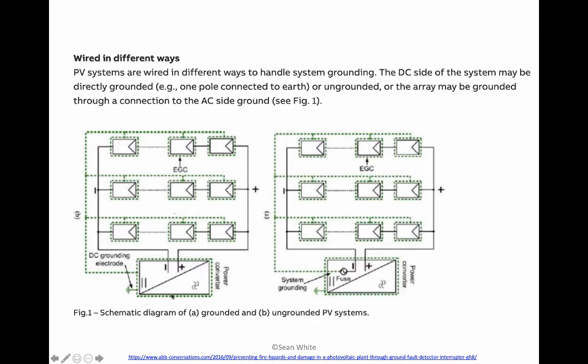We used to call these kinds of inverters European inverters because they were using them a lot in Europe, but Americans, we were afraid of them. They were called ungrounded in the National Electrical Code, and ungrounded sounds kind of scary to somebody that's a traditional old-time electrician. However, since the formerly known as grounded inverters, now known as fuse grounded, functionally grounded inverters, there were some fires, and some of those fires didn't kill anybody that anybody's heard about, but it's just not good to be starting fires. And if it was a fire in a ground mount, it's probably not that big of a deal anyway if you're talking about a giant utility scale system, because they have so many checks in place.